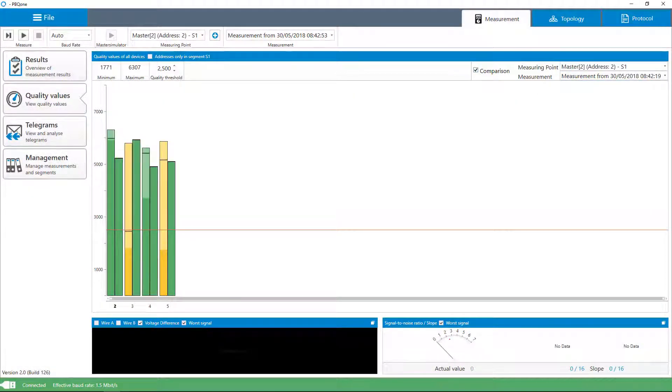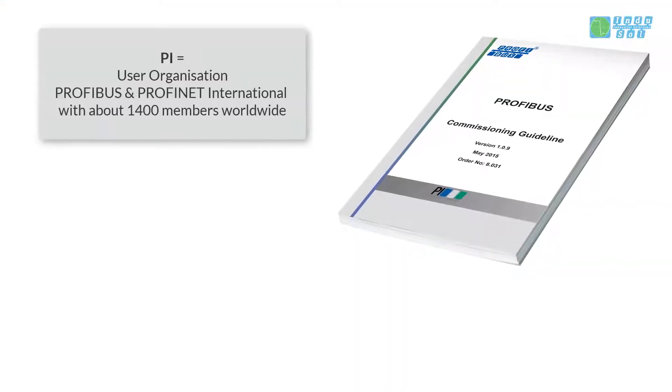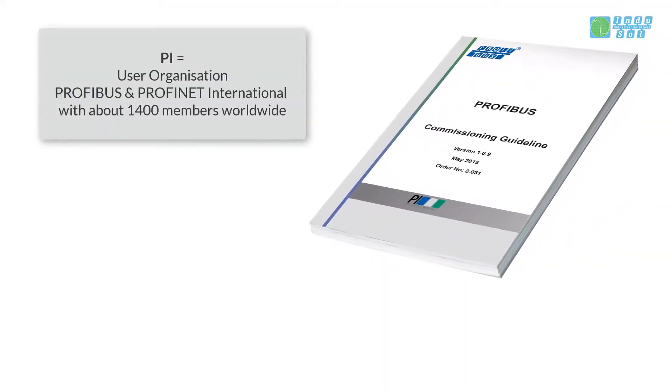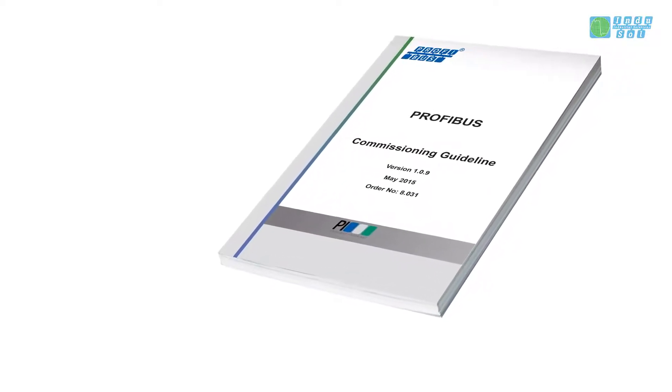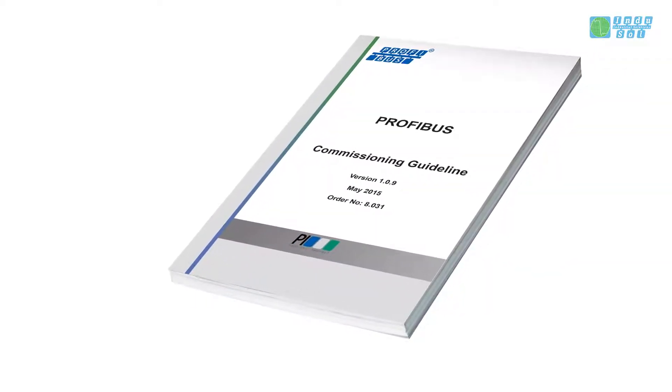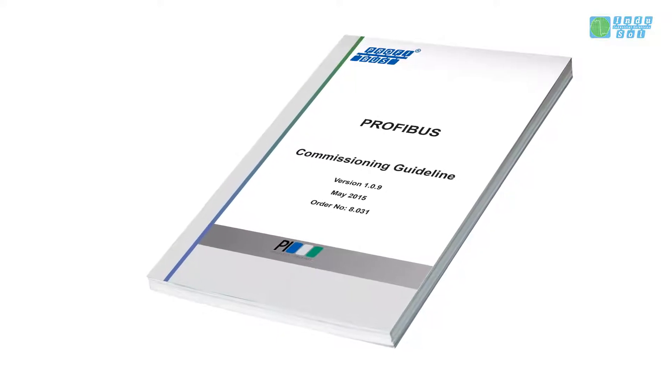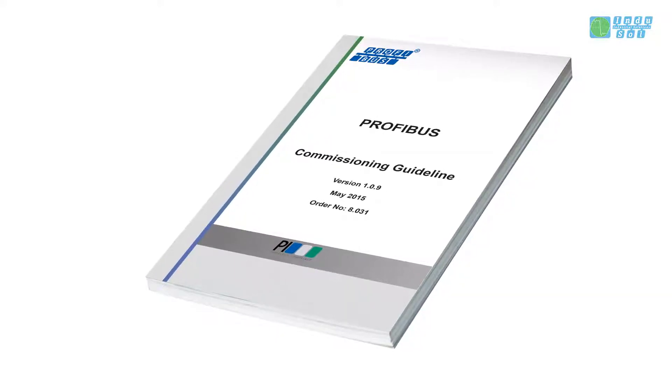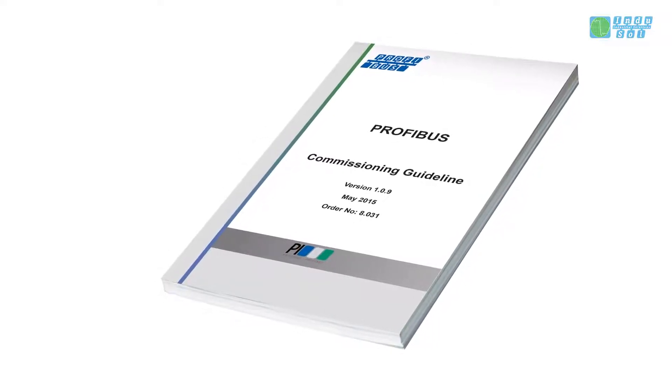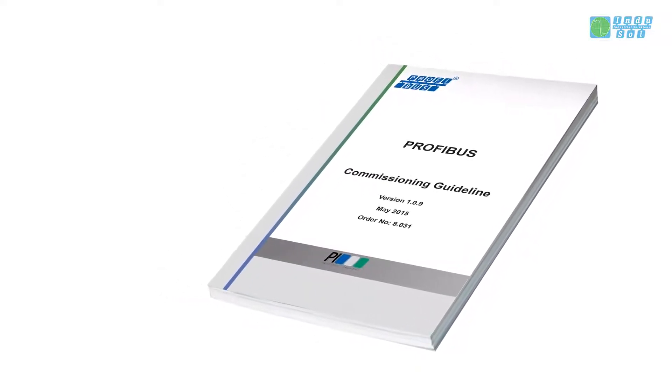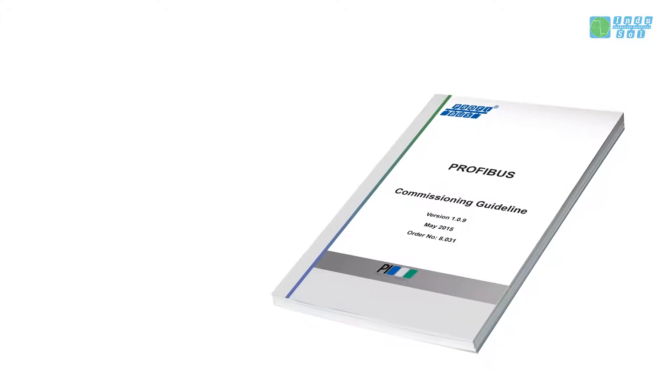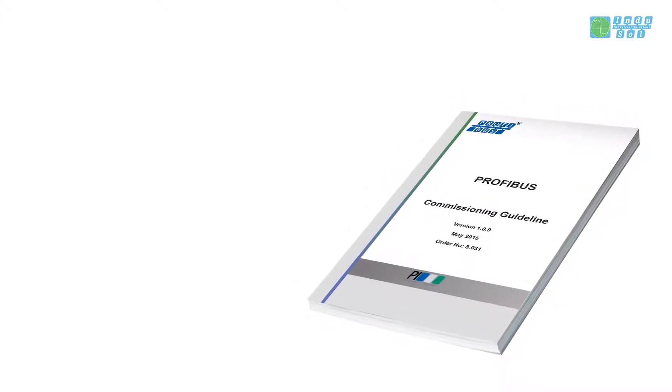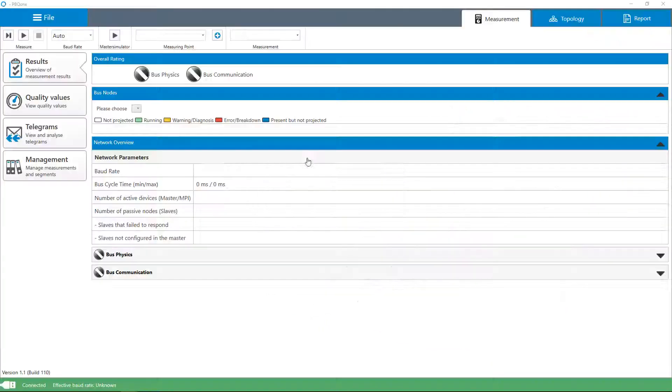In its Profibus Commissioning Guideline, the PI recommends that the communication quality is evaluated during the commissioning of a new system or after a system modification, to document the status quo and as a basis for subsequent measurements. Changes in the physical condition can thus be detected at an early stage and a before and after comparison can be made in the event of a fault.